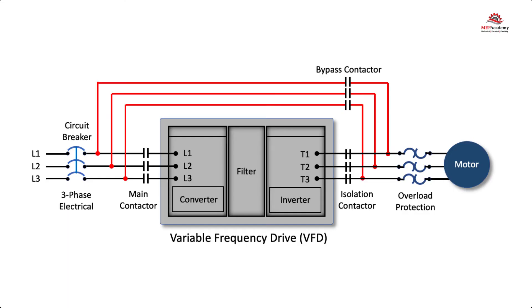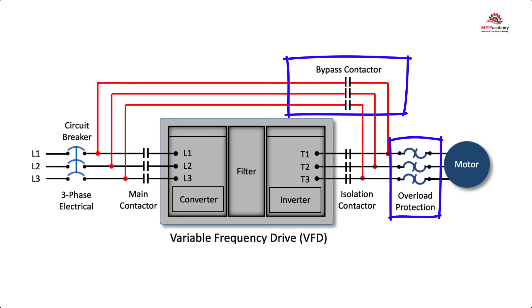Here are some of the VFD components — starting with bypass. The bypass provides a means for circuiting around the drive and providing power to the motor. Be sure that in bypass mode, the motor still has some form of overload protection. Purchasing a bypass adds substantial cost to a VFD. If it's not needed or you can afford some downtime with the equipment, then avoid purchasing a bypass. Or if you have several VFDs of the same size and horsepower, just purchase an extra drive for emergency replacement — it'll be cheaper in the long run.